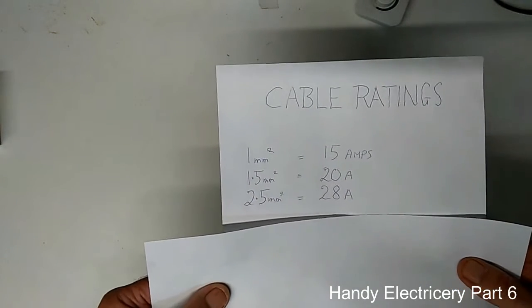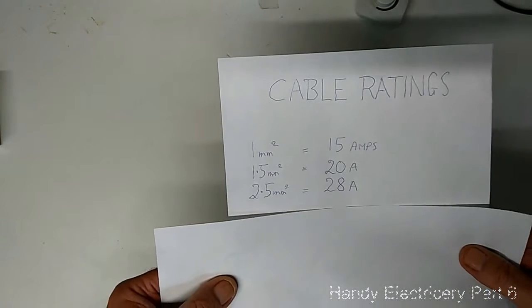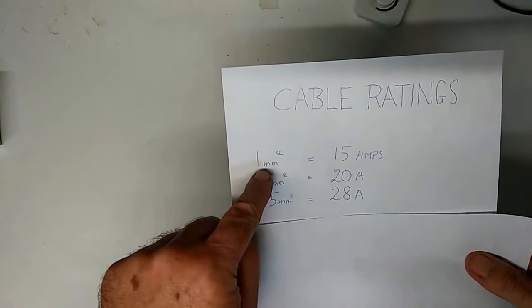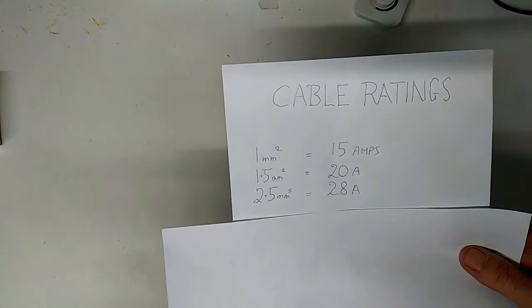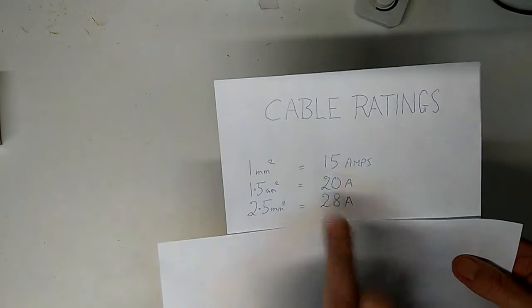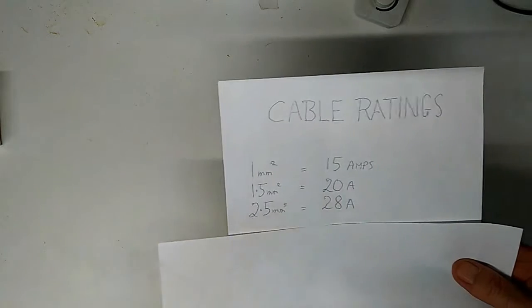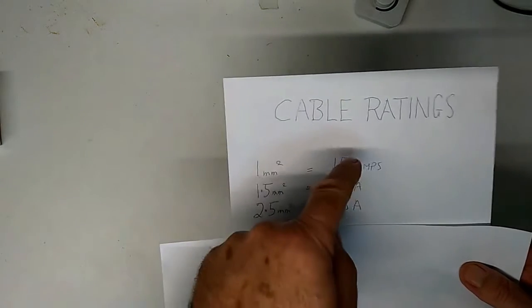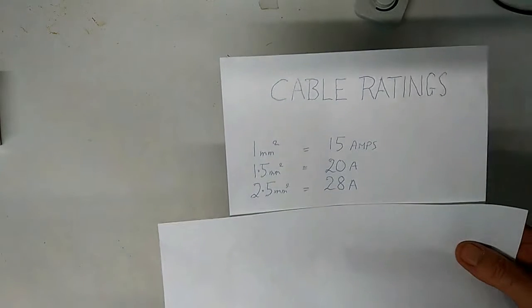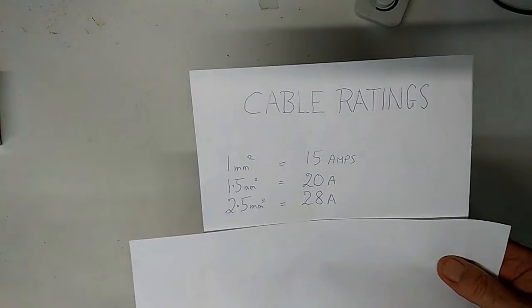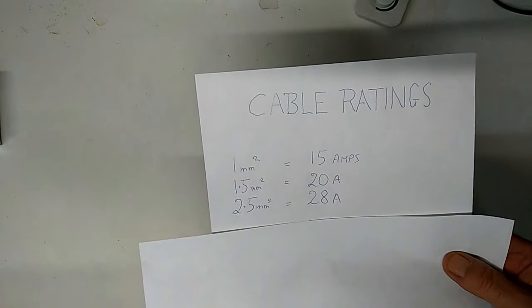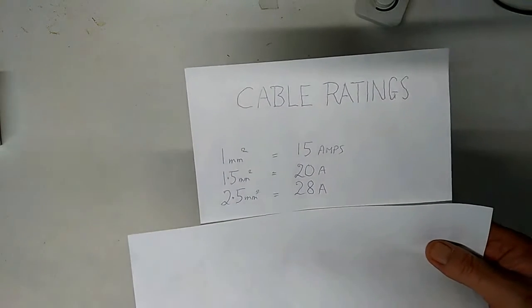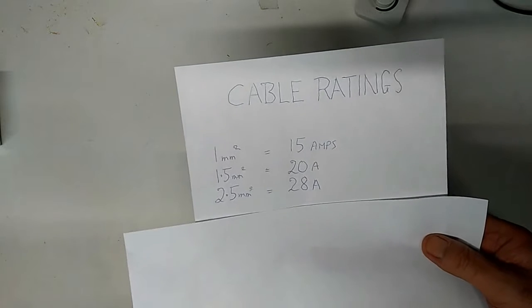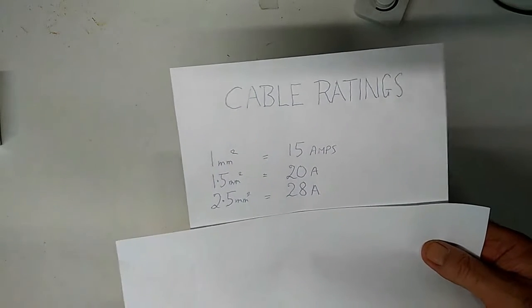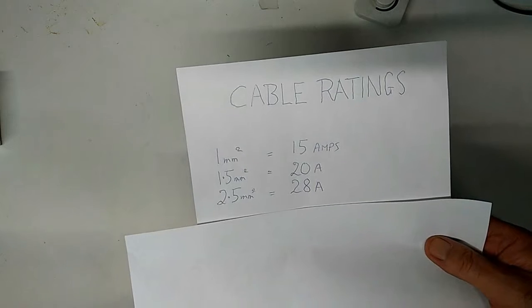These are typical mains cable ratings. 1mm squared is the smaller lighting size of cable, and that can typically pass 15 amps. These figures can vary depending on whether the cable is enclosed in a metal conduit, underground, standing on the surface in free air. It's all to do with the heat dissipation, because a cable has resistance.